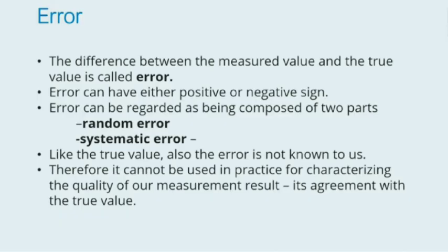It's also the case with a pipette. If there is an error in the pipette because you have not stored it at the correct temperature. They're generally calibrated at, say, 20 degrees. And if we have been storing them at 37 degrees, due to the heat of expansion, there might be some change. That is a systematic error.